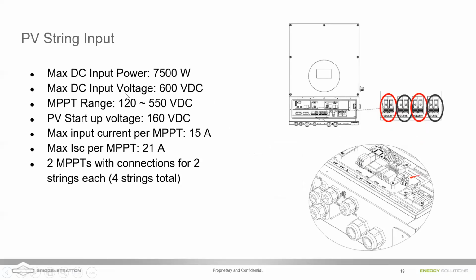As far as PV inputs, there are 2 MPPTs, and each one is going to have 2 connections for the positive and 2 connections for the negative. So really, you can input up to 4 strings into this one unit here. So that's going to avoid, again, what we're trying to do here is avoid you as the installer having to source additional components and having to wait to see these components shipped from overseas and put additional things on the wall that are going to mess up the install. We've really wanted to include as many things as we could within the inverter unit itself. So again, there's 2 separate MPPTs with 4 total PV string inputs.